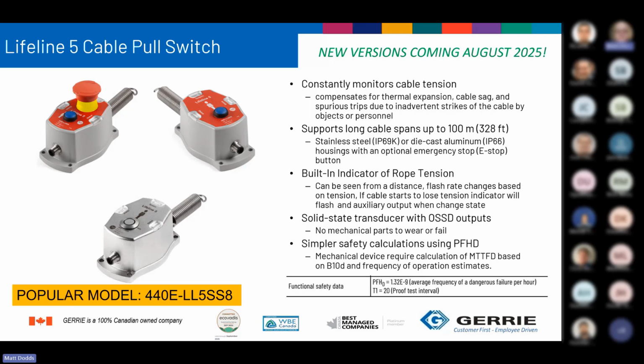So these constantly monitor cable tension, and they compensate for thermal expansions, cable sag, and spurious trips due to inadvertent strikes of the cable by objects or personnel. Currently, they span up to 100 meters, and there is a stainless steel IP69K version. Built-in indication of rope tension, talk about that in a minute. Solid state transducer with OSSD output. So again, series connectable, no mechanical parts to wear or fail.